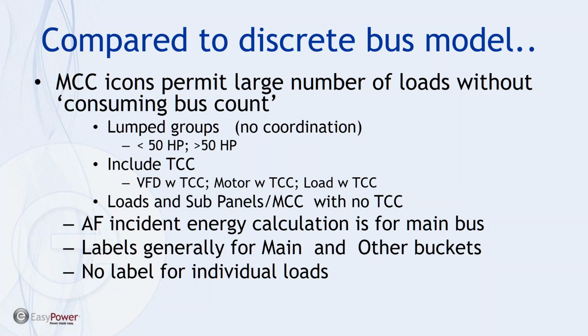The tools also allow the ability to group or lump motors into groups, and this is available both as a standalone motor representation on a discrete bus and in the motor control center's selection of loads. In terms of lumping the motors, these can be grouped in less than 50 horsepower and greater than 50 horsepower buckets. The ability to include the time current characteristic curves for both VFDs, motors, and loads is available, and we'll talk a bit about that in the motor control centers. And then there's also the ability to outboard or set up loads or subpanels without TCCs.